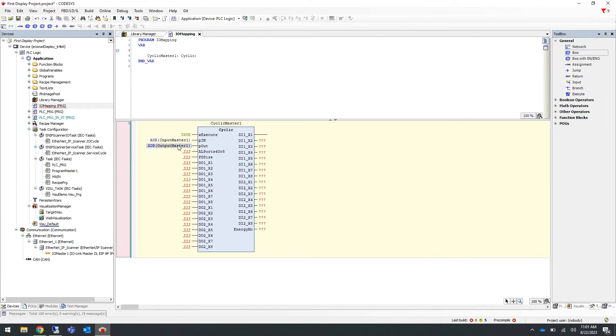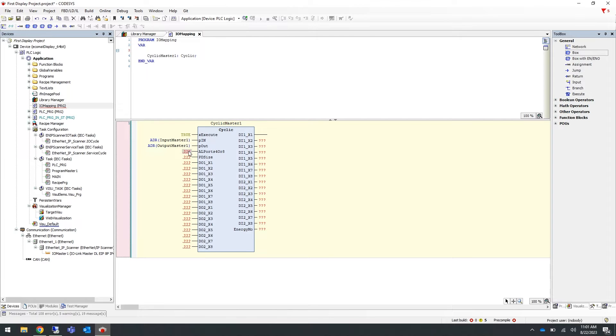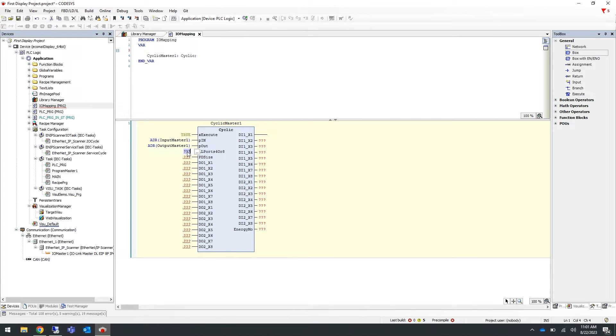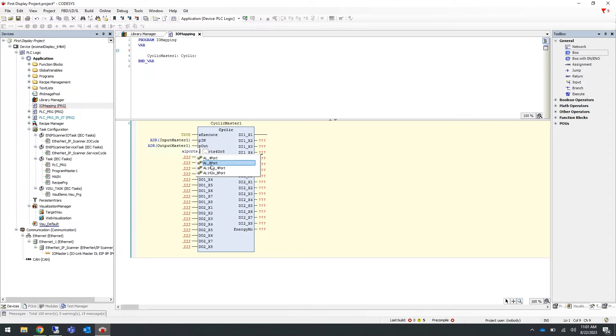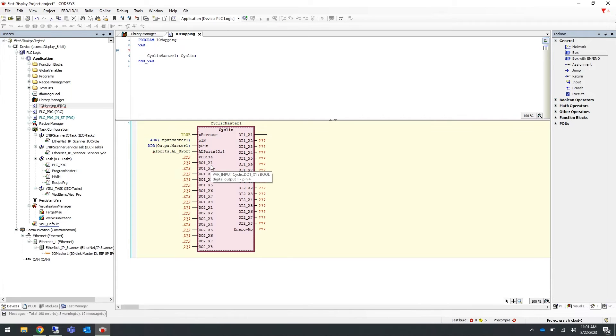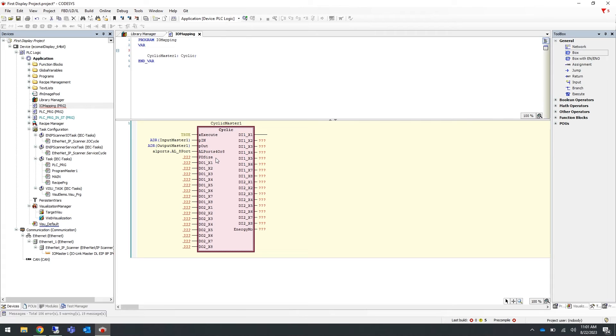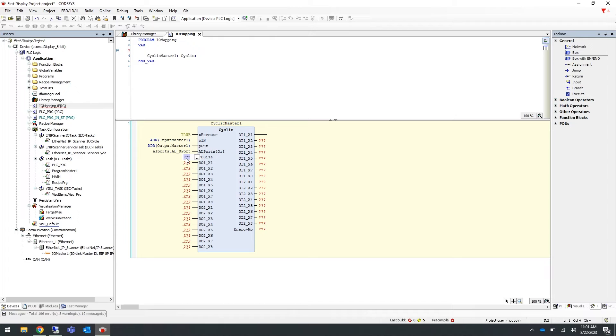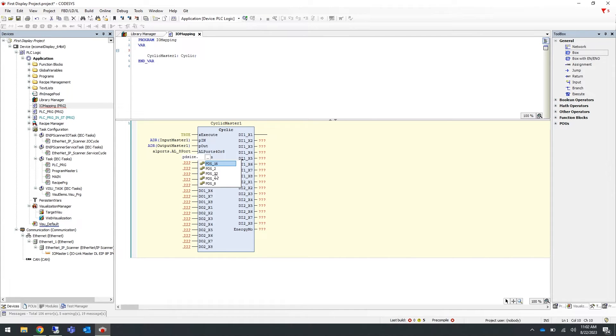The next variable we need to configure is the AL ports four or eight, and this is referencing the number of ports your IO-Link master has. The default setting is eight and we are going to keep it for this setting. Click on the question marks and type in AL ports and then a period, and you will see the different options there. We're going to keep it set for eight ports so we will select AL_eight_port and press enter. The next variable is PD size, which is the process data size of your IO-Link master. Type in AL PD size and then period, and you will see the different options available. The factory default is PDS_32 and we are going to keep it for this setting.